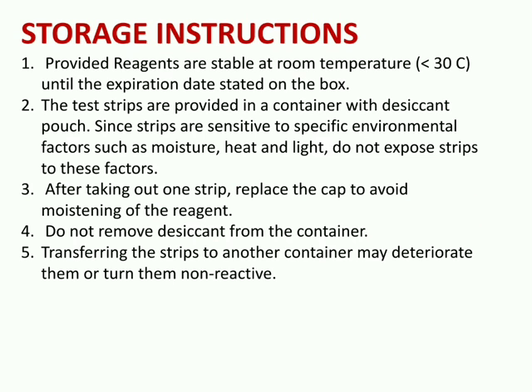Storage instructions for dipsticks: the provided reagents are stable at room temperature until the expiration date stated on the box. The test strips are provided in a container with a desiccant, since the strips are sensitive to environmental factors like moisture, heat, and light — do not expose the strips to these factors. After taking out one strip, replace the cap to avoid moistening of the reagent. Do not remove the desiccant from the container, and do not transfer strips to another container as this may deteriorate or make them non-reactive.